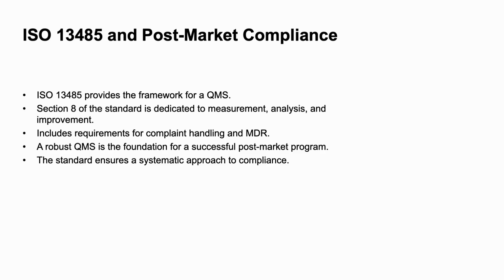ISO 13485, the international standard for medical device quality management systems, provides the foundational framework for a robust post-market compliance program. While the entire standard is relevant, Section 8, titled Measurement, Analysis, and Improvement, is particularly important for post-market activities. This section requires manufacturers to have documented procedures for complaint handling, medical device reporting, and a closed-loop CAPA system. The standard also requires a manufacturer to use post-market data to identify opportunities for continuous improvement, such as changes to product design or manufacturing processes.